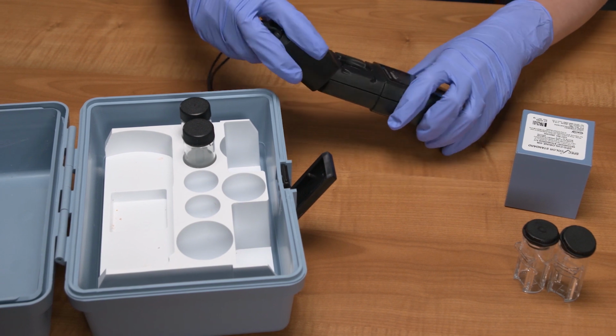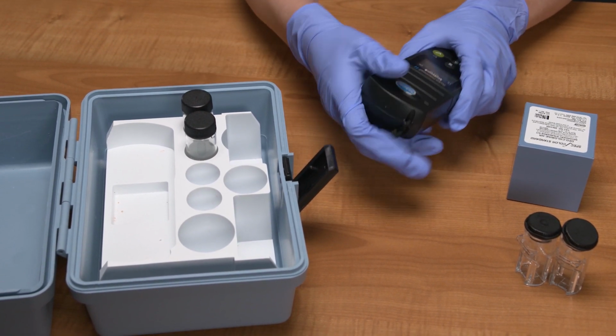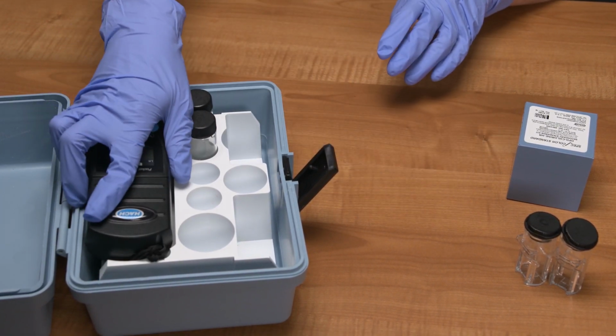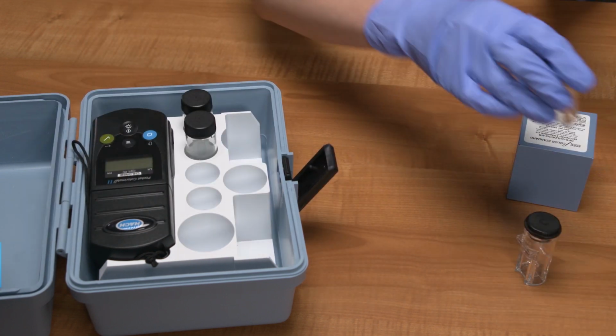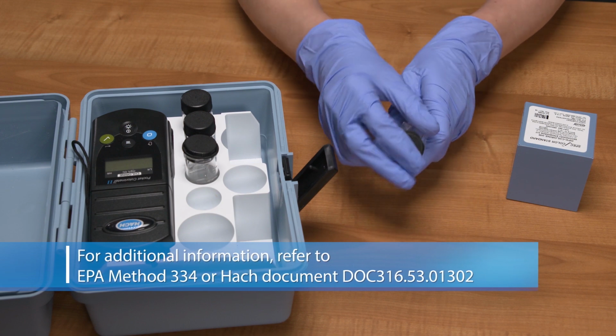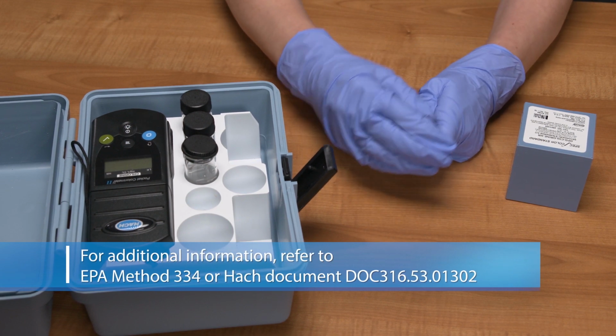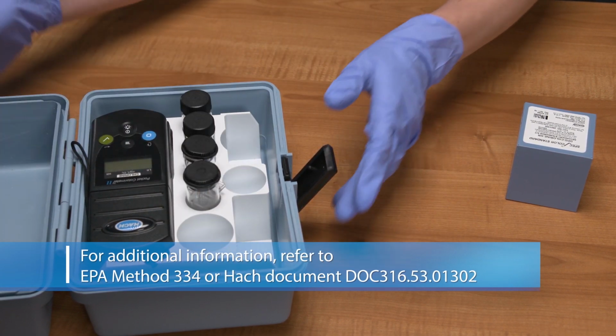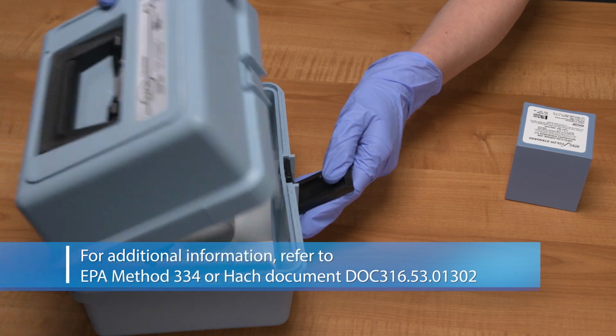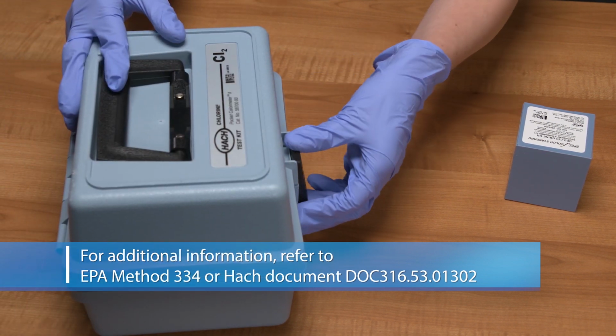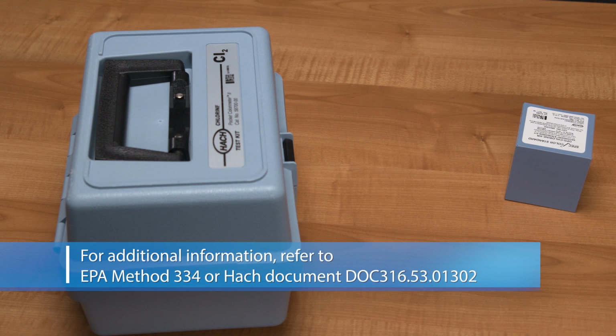Be sure to properly document Method 334 steps, consistent with your state or local regulations. For additional information, or for the method of performing a calibration verification check for an online continuous chlorine analyzer, refer to EPA Method 334 or the equipment manufacturer's procedure, such as HACH Document DOC316.53.01302.